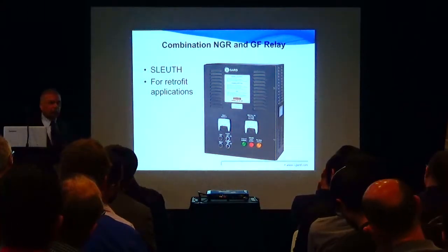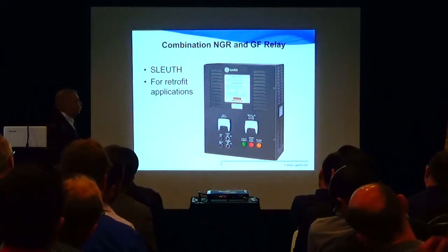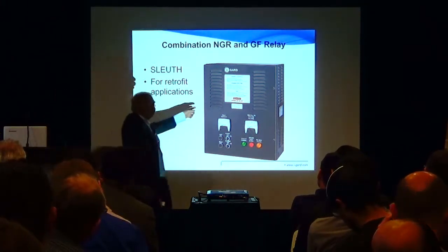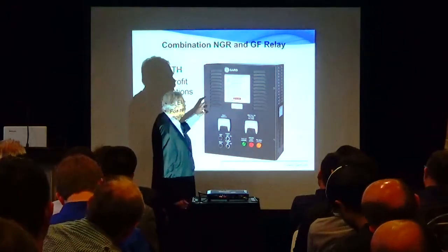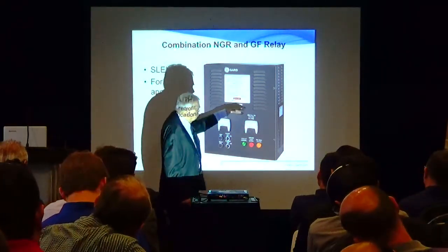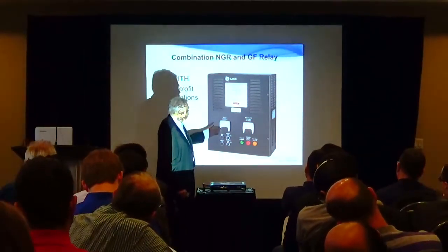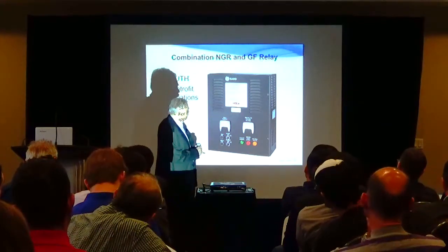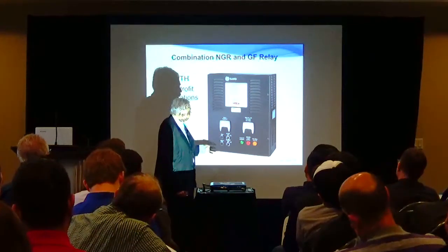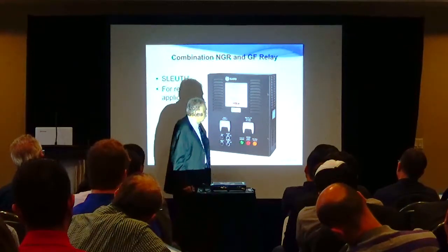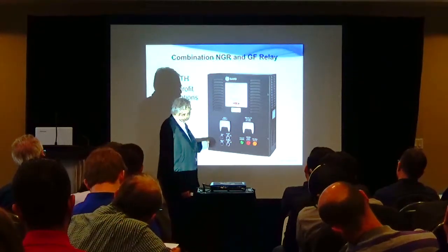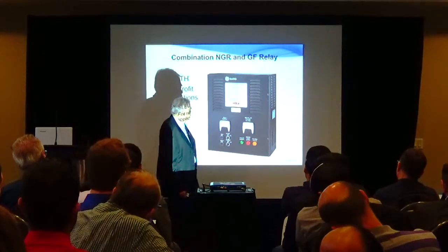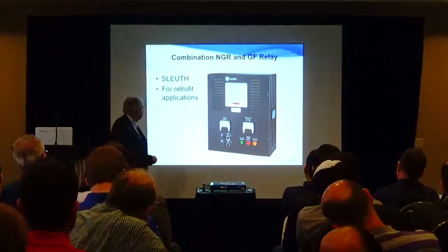Okay, so i-Gard assembles the equipment in boxes, as you will see on the floor. This box contains a neutral grounding resistor. It's wall mounted, with ventilation holes and a barrier, and the controls are below. When the ground current appears, you get a red light to indicate that you have an alarm. If it was a temporary situation, the light goes from red to amber. And on the front, if you want to locate the fault, you start a pulsing, then you go find it, and then you can reset the bus.